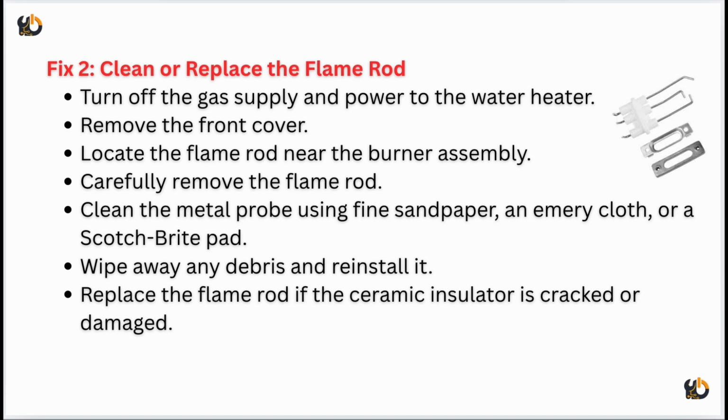Then carefully remove the flame rod and clean the metal probe using fine sandpaper, an emery cloth or a Scotch-Brite pad. Then wipe away any debris and reinstall it, and replace the flame rod if the ceramic insulator is cracked or damaged.